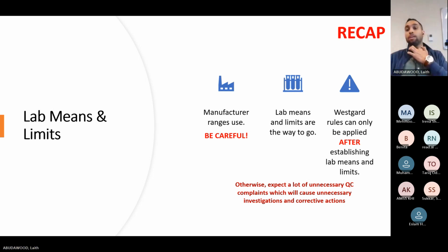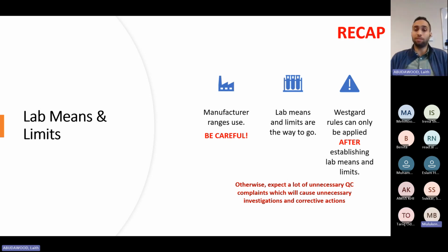That's one thing. Now, a lot of customers will tell you, okay, I want to apply Westgard rules. I want to have better control over my QC. I want to have higher quality of results. Please remember a very important point. Westgard rules are usually not meant to be used with manufacturer ranges. They are meant to be used with lab means and lab limits, not with manufacturer ranges. If you apply Westgard rules with manufacturer ranges, then, well, I have bad news for you. You are going to suffer for a good while, if not all the time you're working with this customer. We will come to the point where I will show you how you really use Westgard rules the proper way.